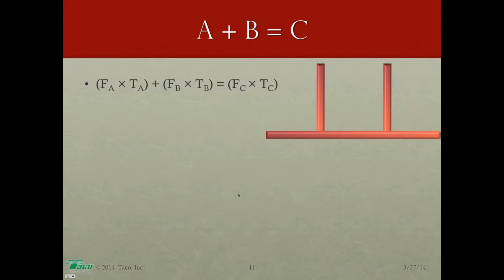Well, we have to identify A, B, and C, right? Well, it's really simple. This is our header return. This is the boiler gazinta, and this is the boiler gazouta, all right? This is the inlet to the boiler. This is the heated water coming out. Well, I want to figure out what my water temperature is going to the system. So this has got to be one of the things. This has got to be C, actually.